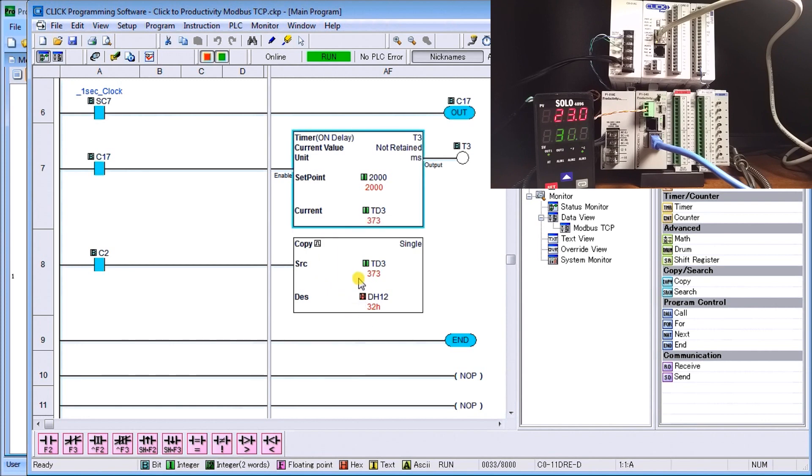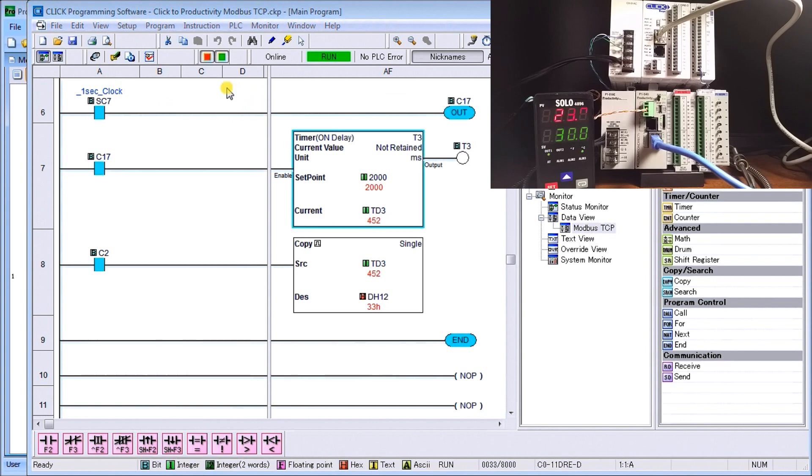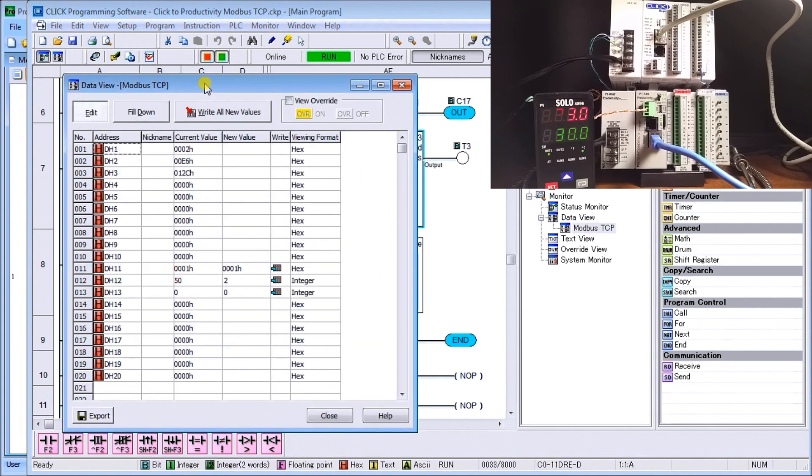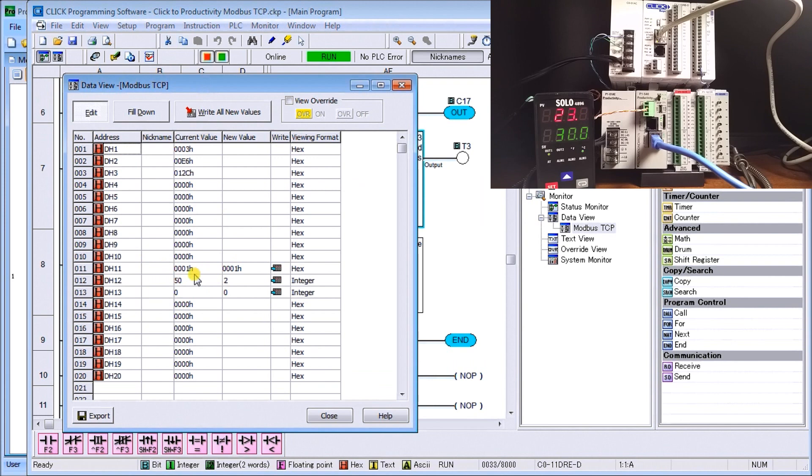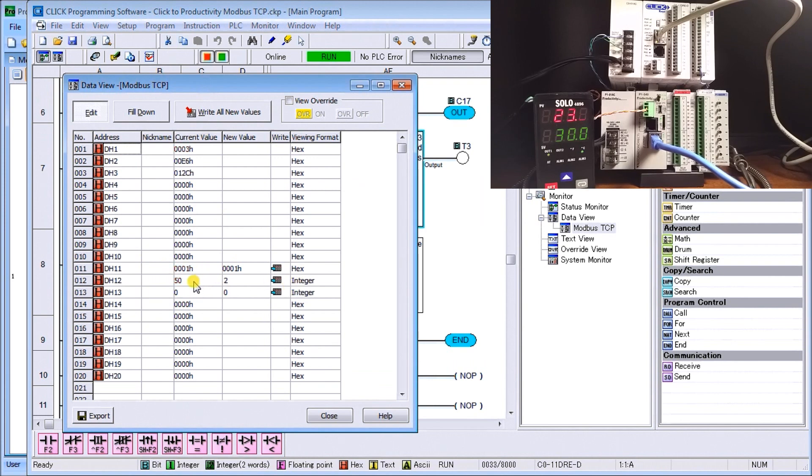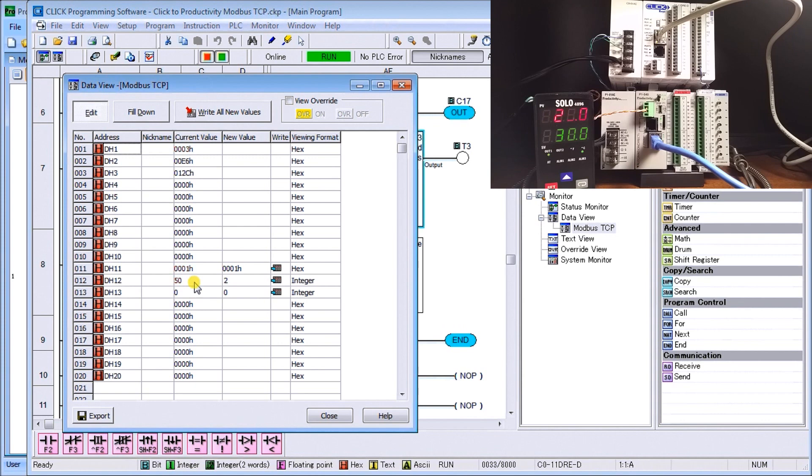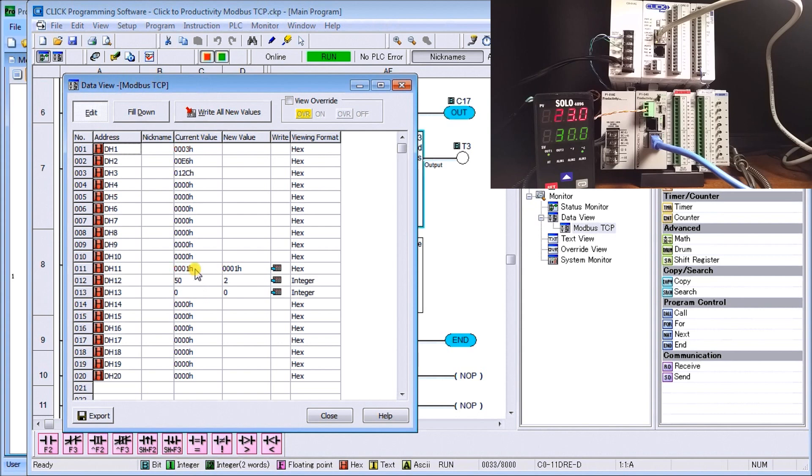If we were to monitor, just call the Data View here, where's our integer? We're looking at 50 milliseconds is currently our update time—51, 50, 51—for our values to read and write 10 registers each. That's how you set up your Modbus TCP: very straightforward, very easy.